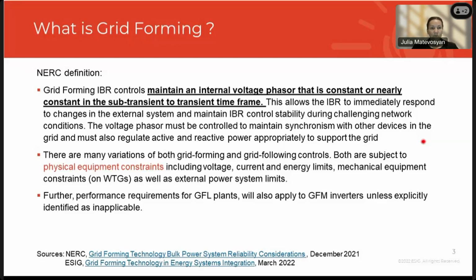There are many variations of grid forming controls as well as grid following controls, and both of these types of controls are subject to physical equipment constraints, including voltage, current, and energy limits. There are also mechanical constraints on wind turbine generators. And then there is a common understanding, as you will see as I'm going through requirements that have been established for grid forming resources, that these performance requirements are in addition to what we currently have for grid following inverter-based resources.